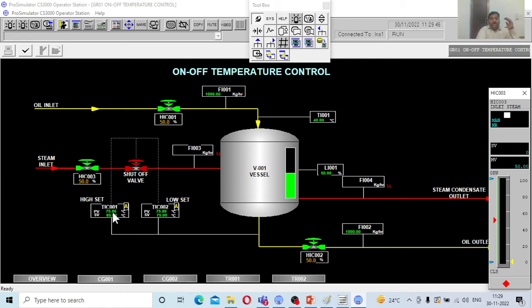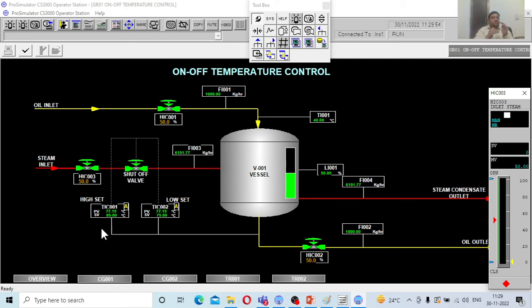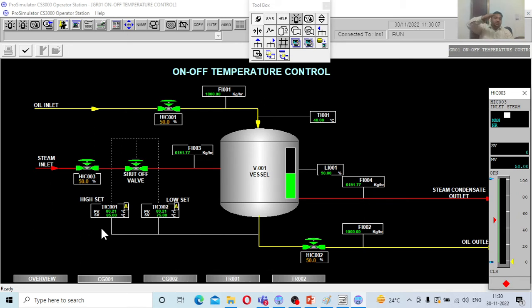Now the process value will fall toward 75. The moment it hits the low set point of 75, the valve will be completely opened again. Then the oil temperature starts rising, and the moment it hits 85 again, the valve completely closes. So this controller cycles between 75 and 85 — that is the on-off control action you are going to observe.